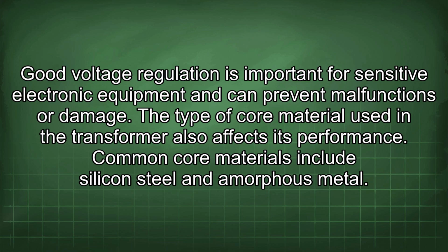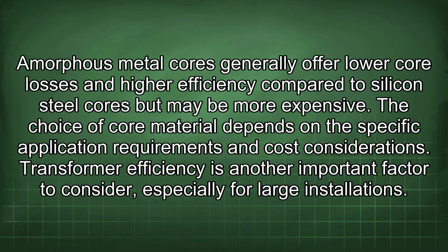The type of core material used in the transformer also affects its performance. Common core materials include silicon steel and amorphous metal. Amorphous metal cores generally offer lower core losses and higher efficiency compared to silicon steel cores, but may be more expensive. The choice of core material depends on the specific application requirements and cost considerations.